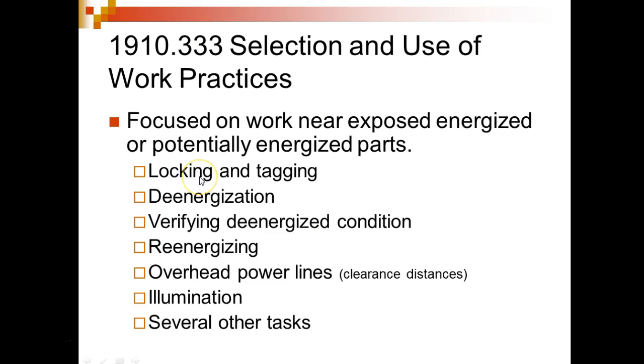333 covers locking and tagging, how to de-energize stuff, how to verify stuff is de-energized, and the procedure for re-energizing stuff, right? Overhead power lines, being careful on those, illumination, and then several other tasks. Of course, we're going to be very interested in lockout and tags, so we have locks for the class. And of course, verifying that you don't have any air pressure or fluid pressure, and you don't have any electrical pressure. So we don't put our life on a lock and a tag.